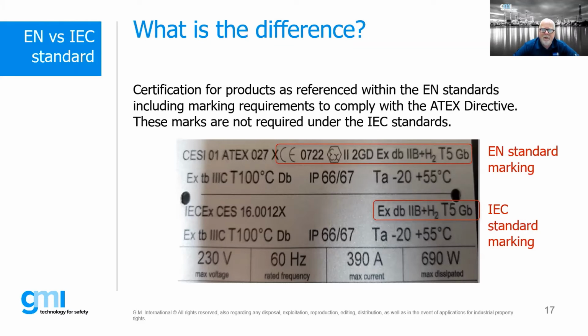So if you look at the top line, you'll see a certificate number. Then you'll see 01, the date the certificate was first issued, ATEX 027X. The CE marking, the 0722 number, is actually the number for the notified body. That's CESI's notified body number, so anything CESI does will always have a 0722. Then you'll see that familiar hexagon EX, then a Roman numeral II, that's for surface industry.